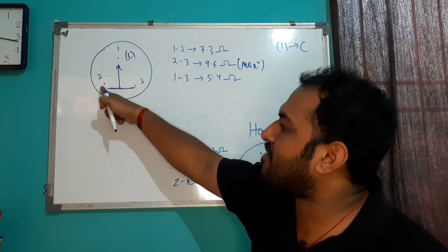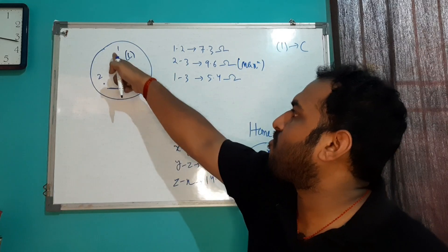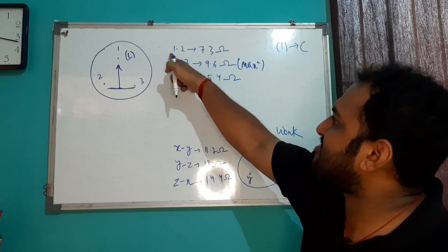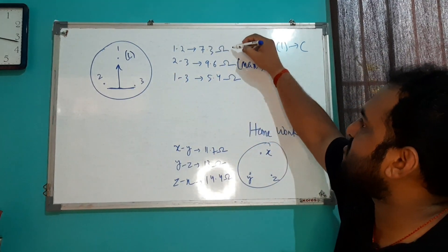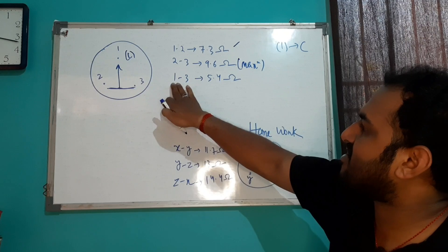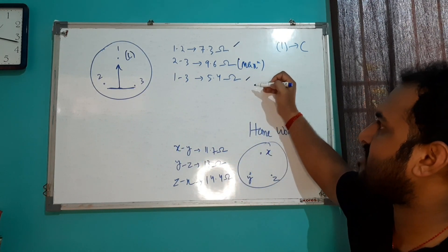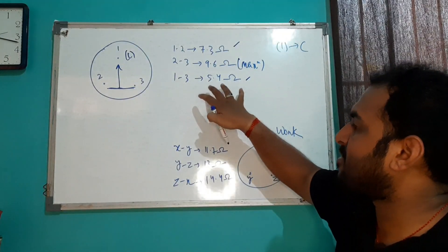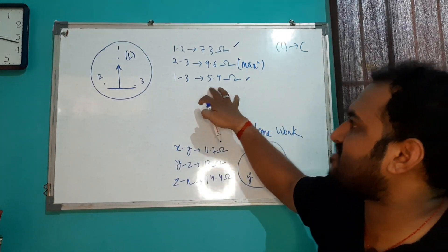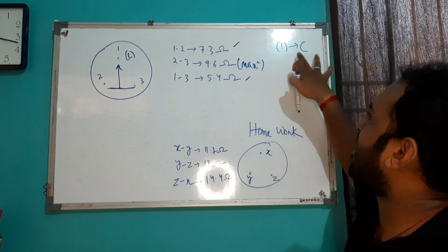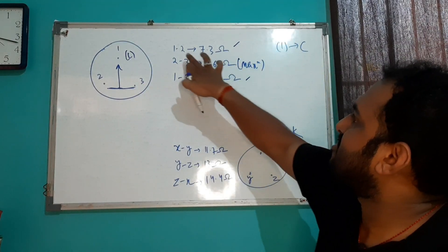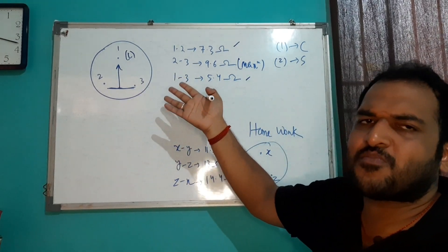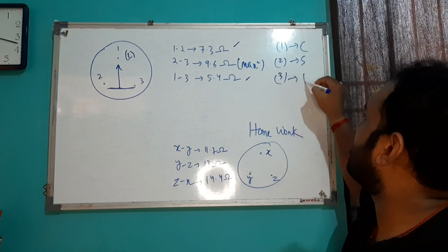Now, with terminal one identified as common, measure resistance from one to two — that gives 7.3 ohms — and from one to three — that gives 5.4 ohms. The higher value (one to two, 7.3 ohms) means two is your starting point, and the lower value (one to three, 5.4 ohms) means three is your running point.